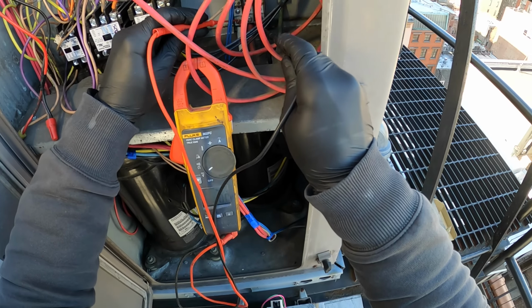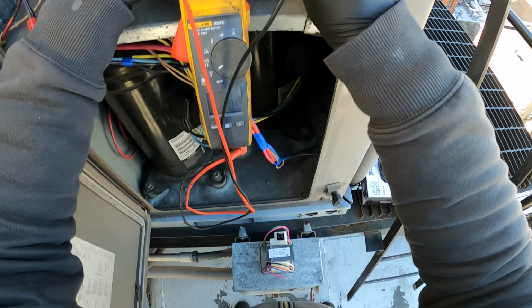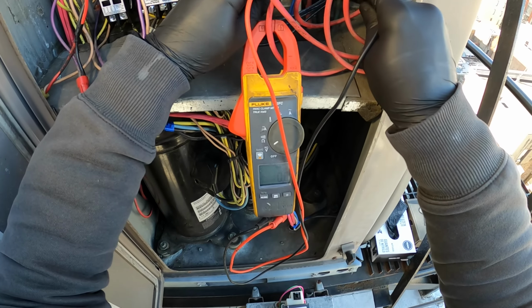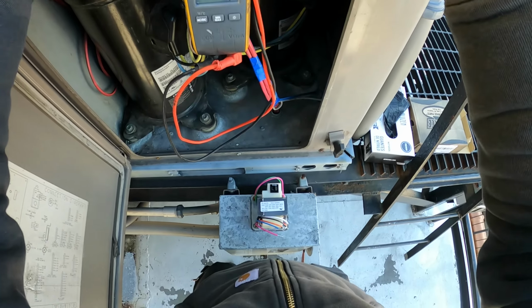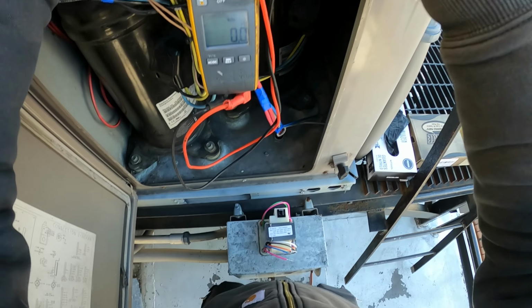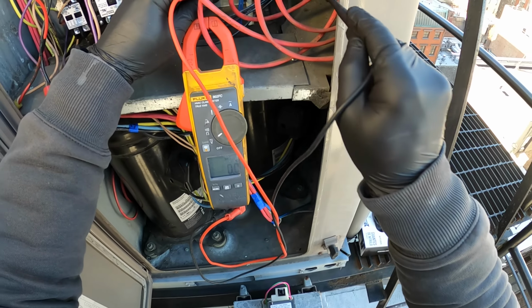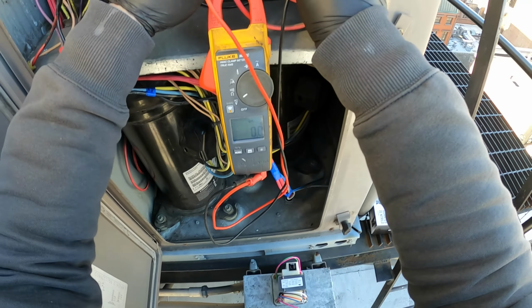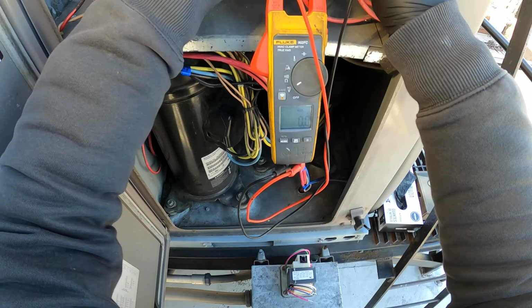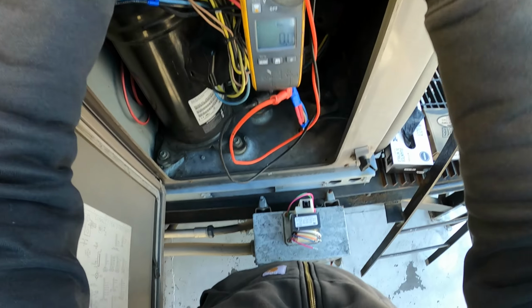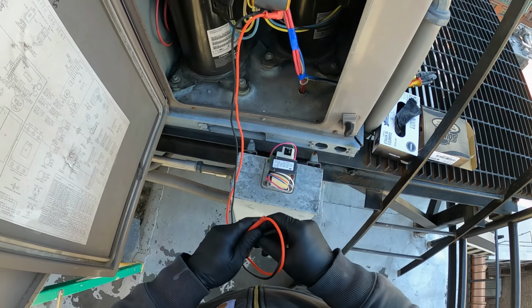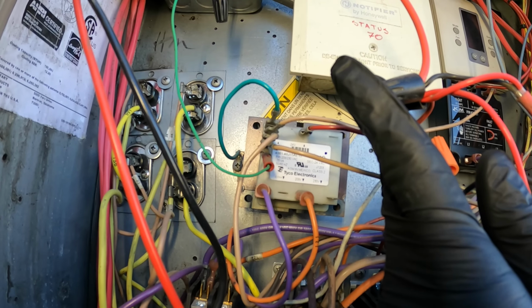This is a three-phase 208 volt system. We're gonna go across the first two legs, 0. Between the first and third leg, 0. Between the second and third leg, 0. And you could also go from each leg to ground, nothing, nothing, and nothing. We're safe to work.